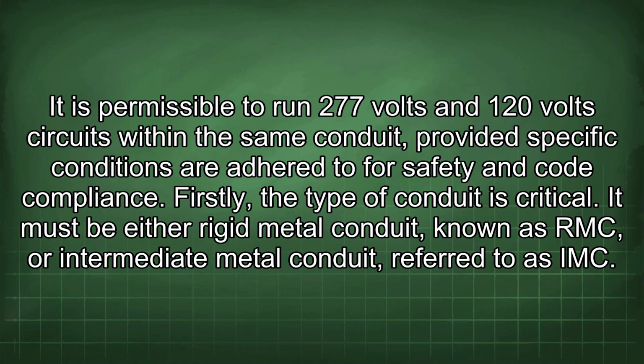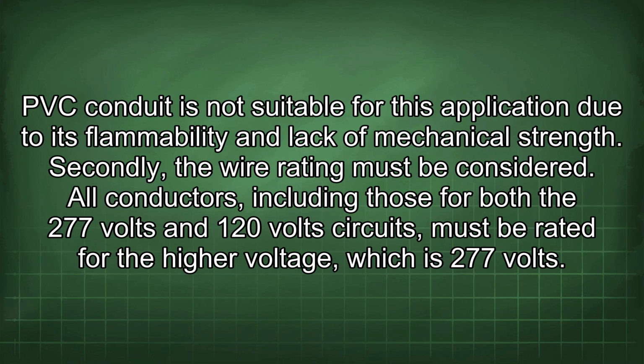It is permissible to run 277 volt and 120 volt circuits within the same conduit, provided specific conditions are adhered to for safety and code compliance. Firstly, the type of conduit is critical. It must be either rigid metal conduit, known as RMC, or intermediate metal conduit, referred to as IMC. PVC conduit is not suitable for this application due to its flammability and lack of mechanical strength.